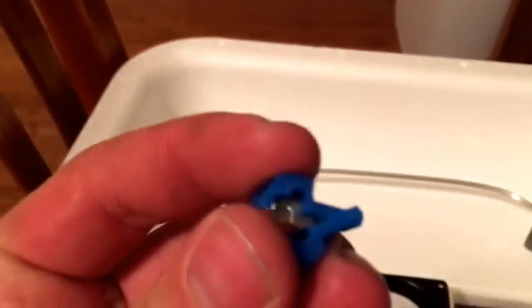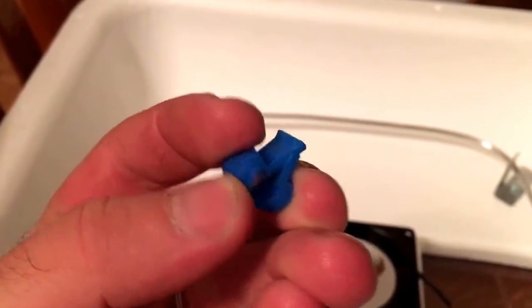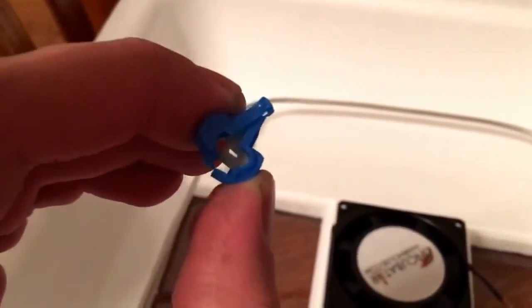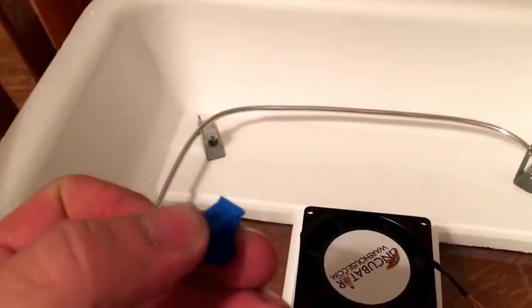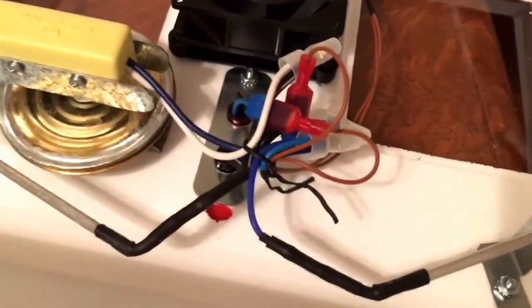Here's my incoming power wire here. I've got this wire that jumps over to the thermostat and this wire jumps directly to the heating element. So you're going to tap into both of these. They send these little quick clip deals and you just snip them onto the wire. They actually cut through the insulation to make an automatic connection for the wire, and then you're able to hook your probes on this wire directly into it.